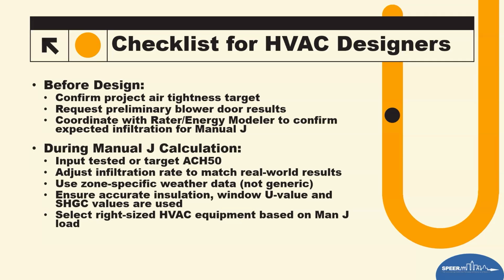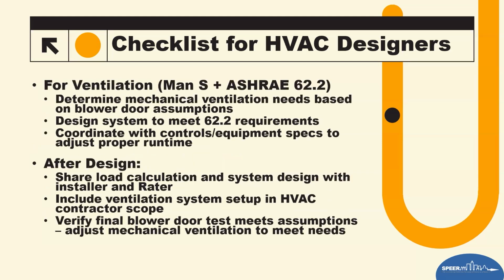Then you make sure the right sized HVAC equipment is based on that load calculation. Right now, you're still assuming it's a 4 ACH house. You don't know yet. You just assume that it is. So you're basing all of this on that assumption. You build all of this. You do Manual J, you do Manual S. You make sure the BTU output of that equipment matches the BTU of the load of the Manual J, and then you turn that in for permit. And then they get a permit and they start to build.